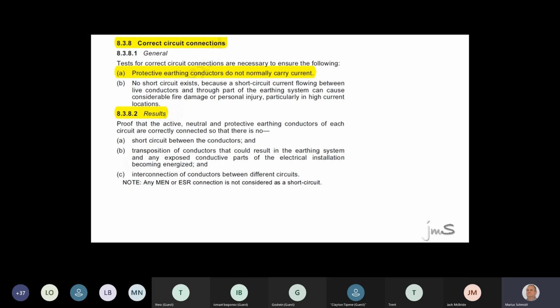Who can remember the days we used to have an MEN board, a DB board? Have you guys ever heard about a link switchboard? A link board was a DB with a link in it. Now, think about this. If 10 amps goes in a phase and you have no link, neutral will be 10 amps. How many amps is on the earth? 0. But if you've got a link in it, you can have 10 amps in the phase, and it's possible that you can have 5 amps coming back between neutral and earth. Now, in that condition, your earth is carrying operational current.